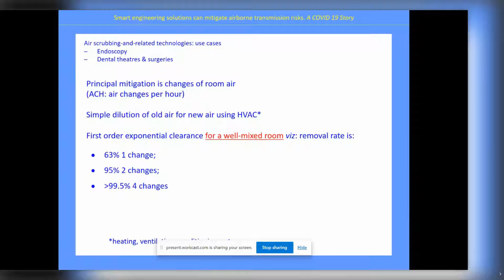63% new air appears after one change of air, 95% for 2, 99.5% for 4. So it's a first order exponential decay of contaminant, pathogen floating around in the room. I'm going to use this expression for a well-mixed room rather often, but you'll see where that goes as we proceed.